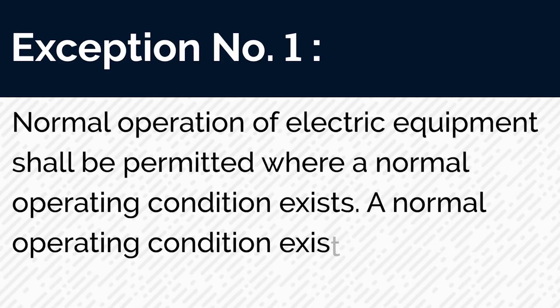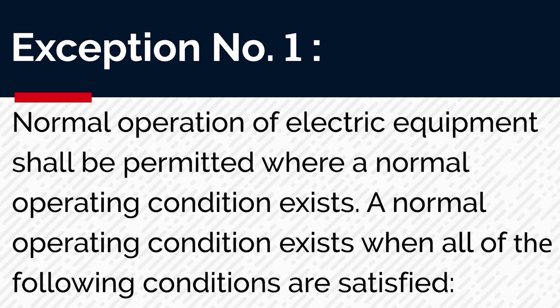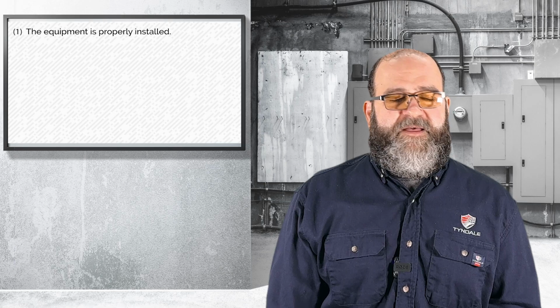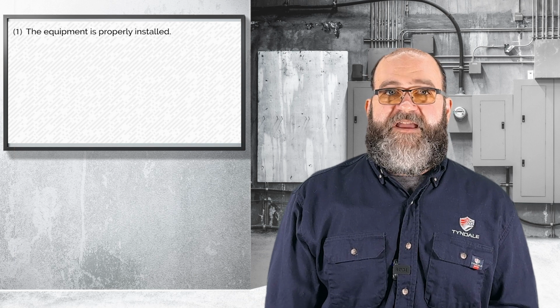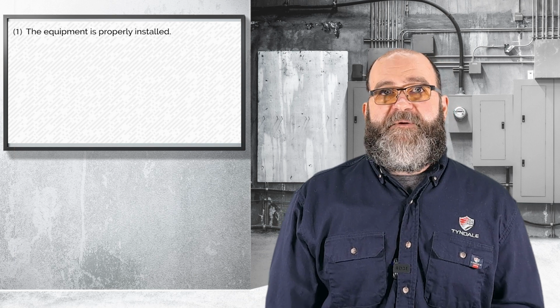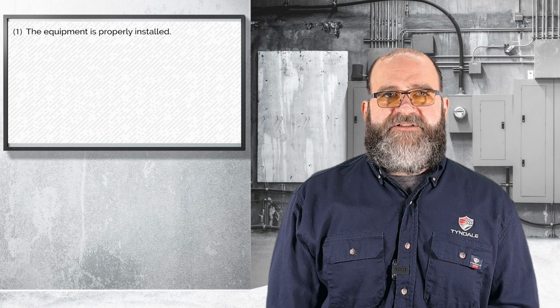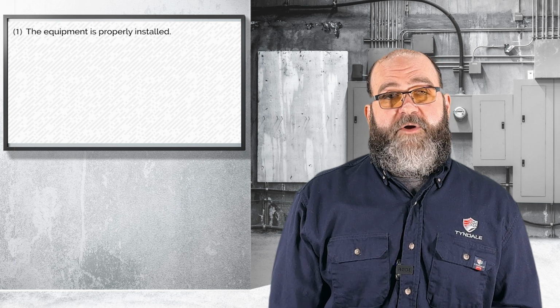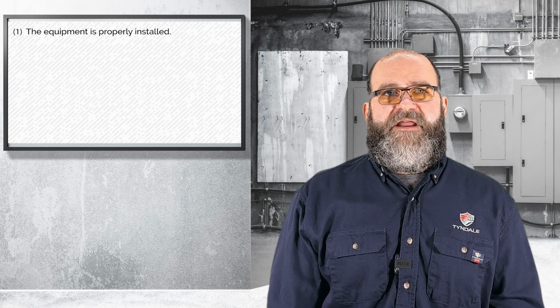The exceptions say normal operation of electrical equipment shall be permitted where a normal operating condition exists. A normal operating condition exists when all of the following conditions are satisfied. Number one, the equipment is properly installed. Now that's going to be per manufacturer, per the 70, per the city codes, per the spec. Generally, that's not an issue. It's typically installed properly. I've seen a lot of equipment not installed properly. That's usually not the rub.